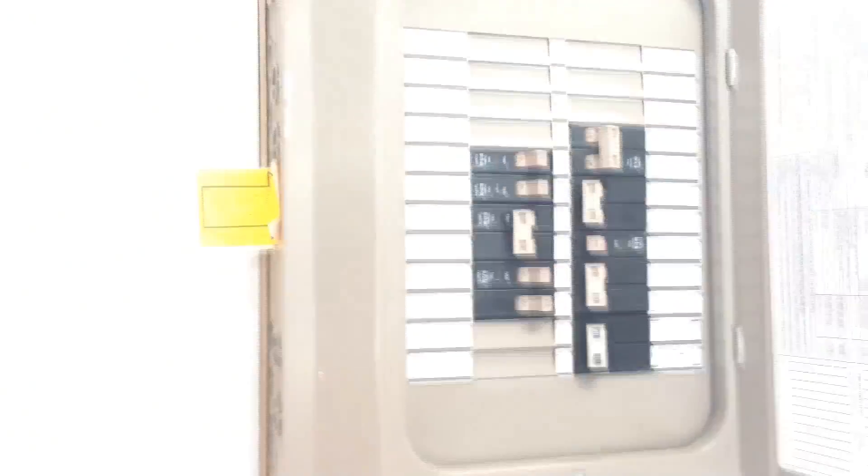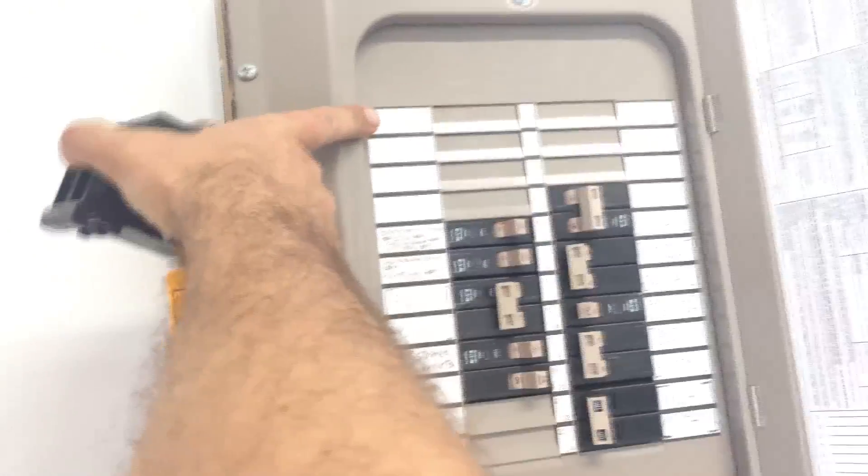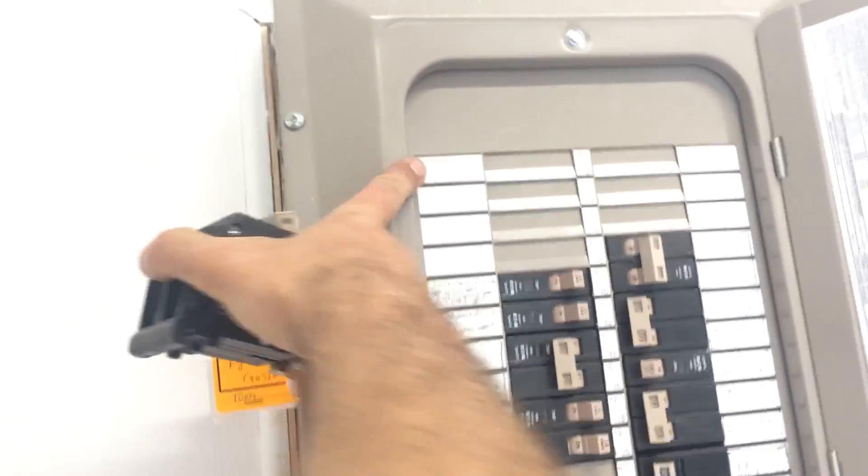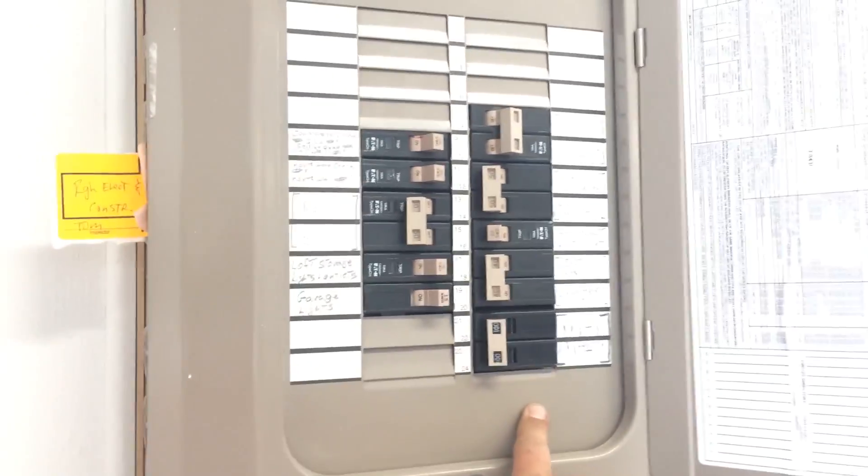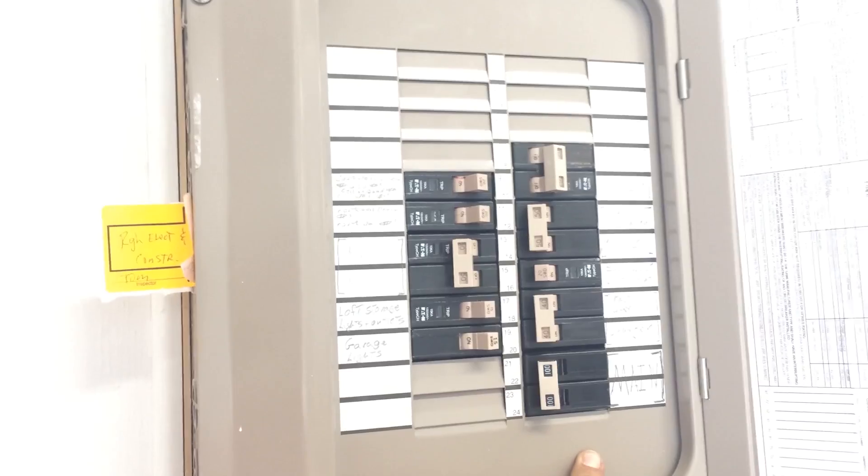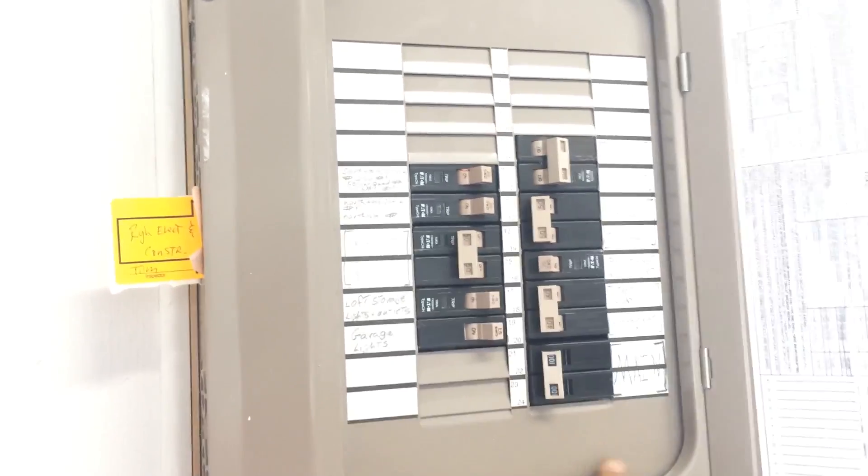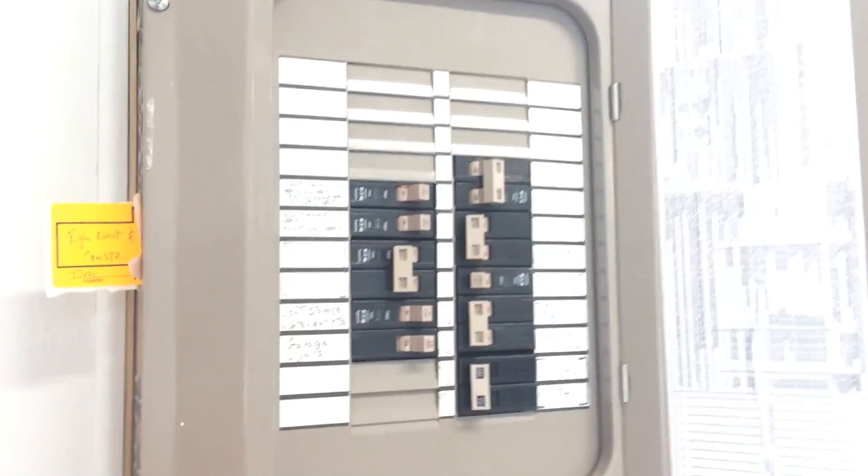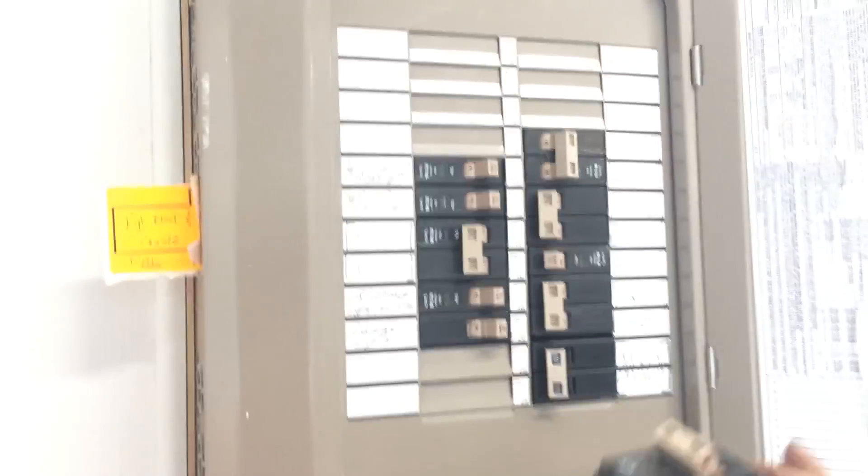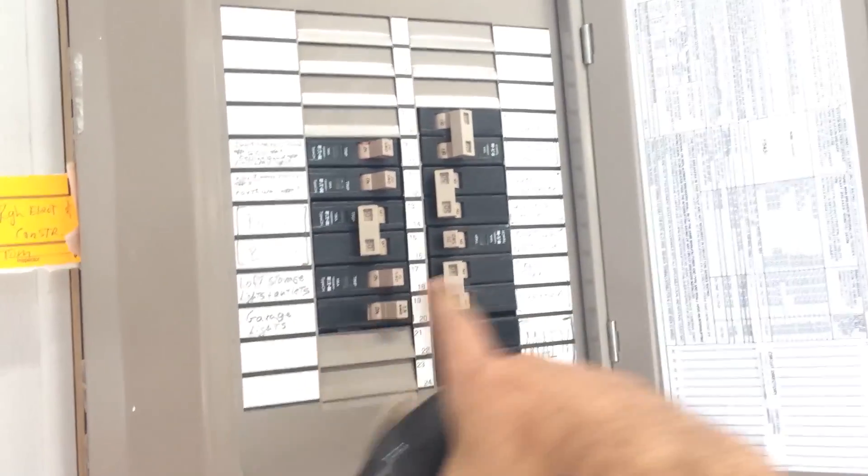So we're going to come through basically right about here, and then over into the main breaker box. And then I've got a 30 amp breaker, which I'm going to install up here because it's opposite of the main breaker. That way any heat from current or anything is dissipated over the entire panel, rather than if I put it here, all the current is in this part of the panel.